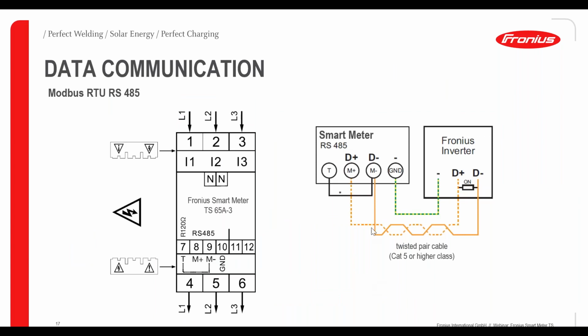So just to sum up, the most important things we mentioned during the installation: we used the twisted pair cable between D- and D+, and for that, Cat5 or higher class is recommended. Then we talked about the protection covers to cover the connection terminals of the smart meter to protect you as an installer when you're working on the data communication pins. We talked about the termination. So you activate the termination on the smart meter by bridging pin 7 and 9, and with that tiny little switch on the data communication card. And we use a shielded cable, and we ground the shielded cable between D-, D+ and minus the ground.